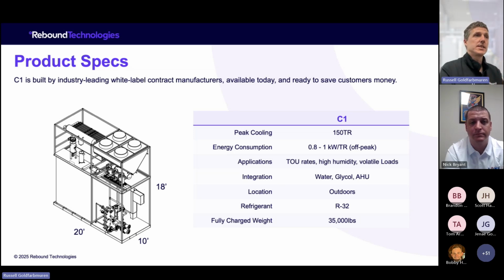While our ice maker is this new technology, the actual equipment that's running it is dead simple, off the shelf stuff. We're running R32, we're running scroll compressors, oil separators, everything you would expect to find in a refrigeration system. And so serviceability is really straightforward. And we're really looking at applications anywhere you have really high time of use rates, you have really high humidity, you have really volatile load, ideally the combination of all those things. Right now everything is contract manufactured, and we're really looking for those initial niche markets where this technology can offer a lot of value because of this ability to do agile cooling.